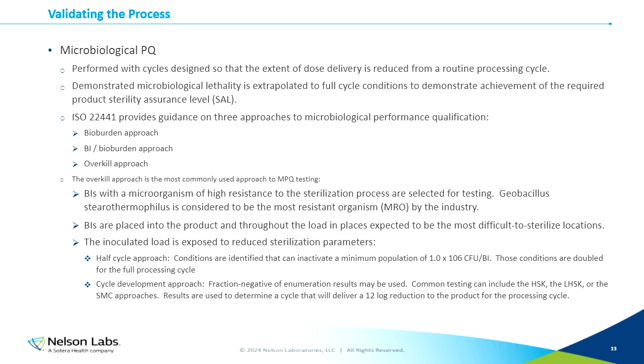We might run fractional cycles. The idea is that we reduce the dose delivery so that we're able to generate results and then extrapolate those results to full cycle conditions to demonstrate achievement of the required product sterility assurance level, or SAL. So ISO 22441 provides guidance on three different approaches to microbiological performance qualification.